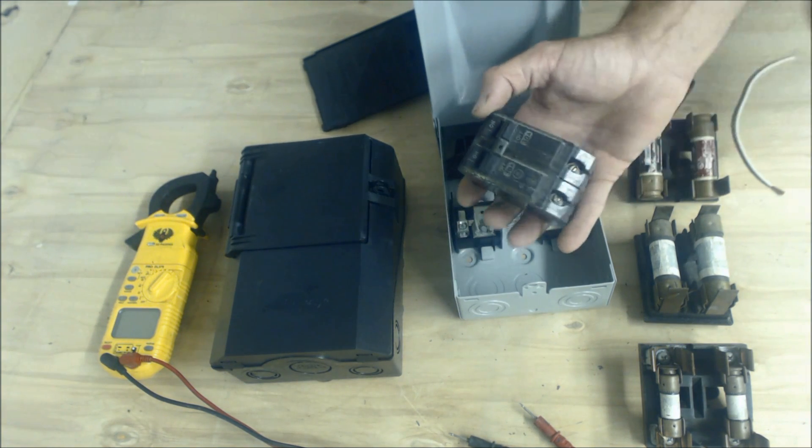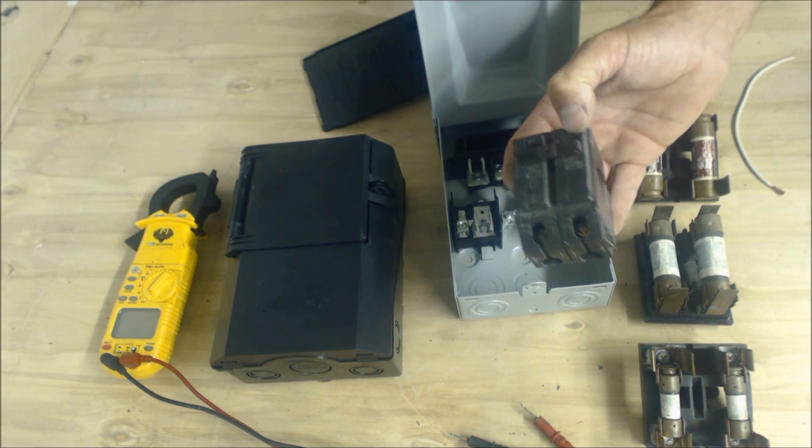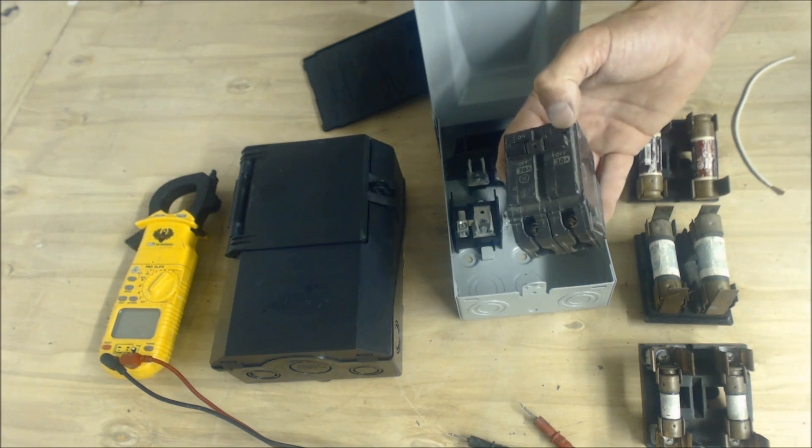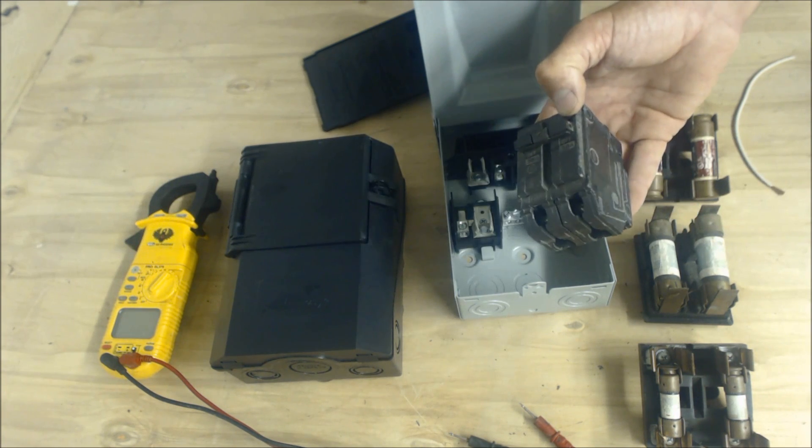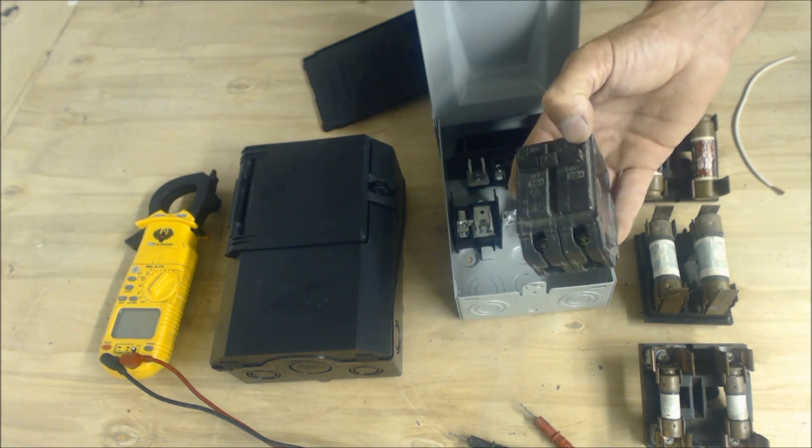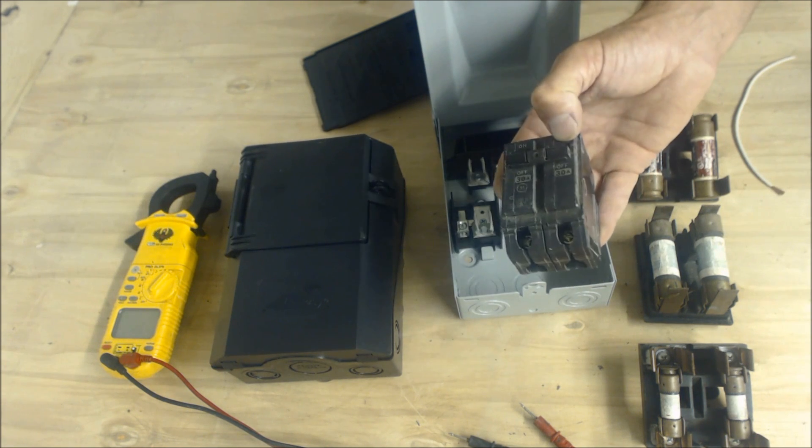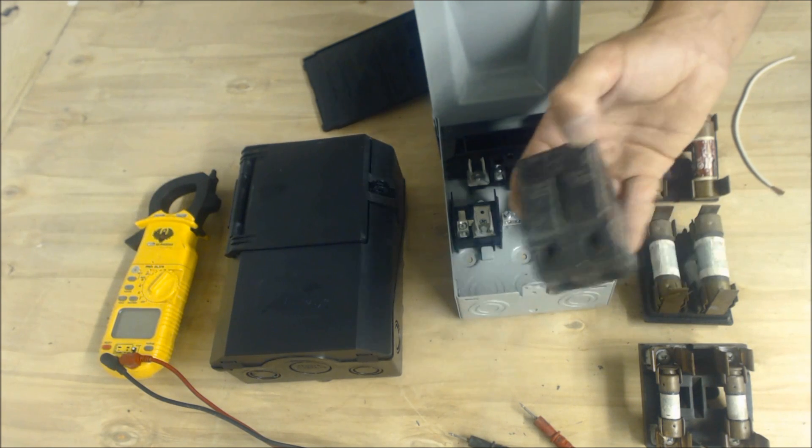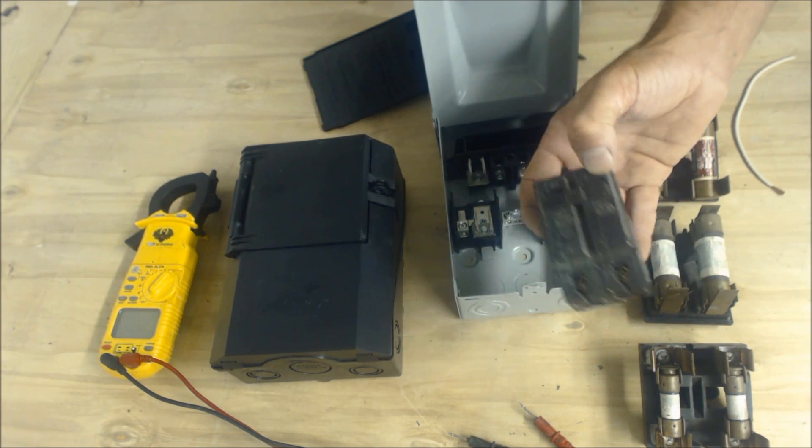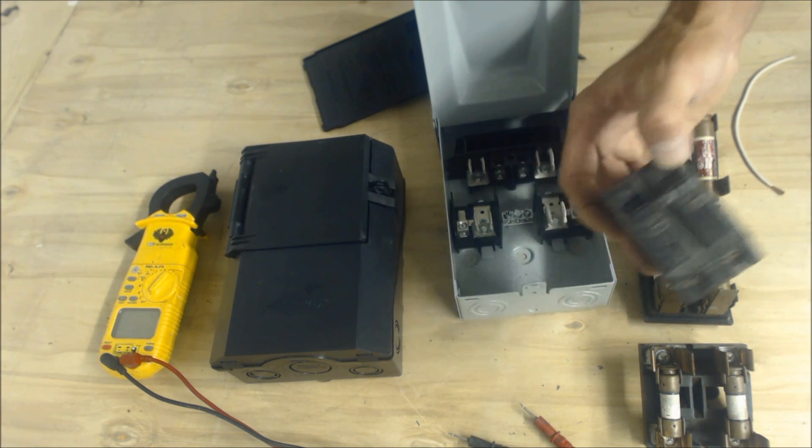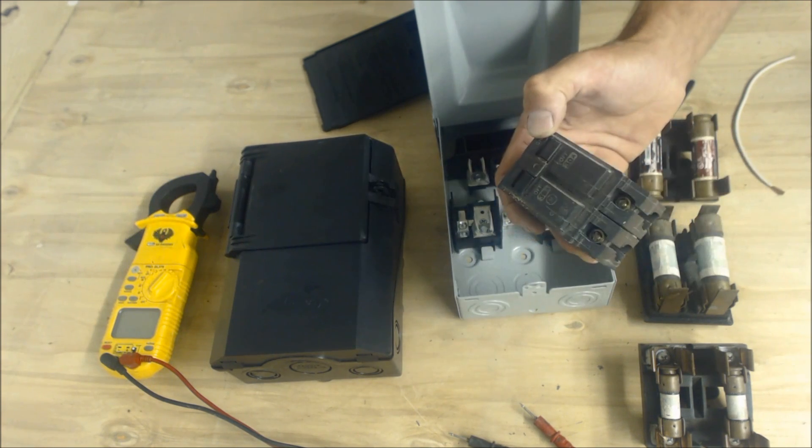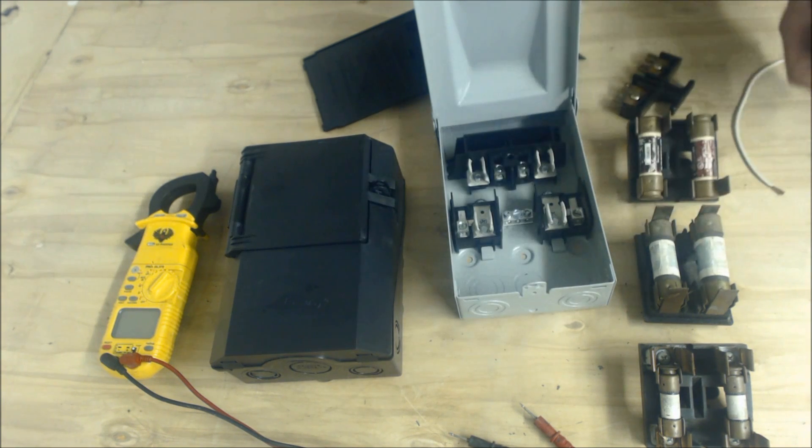Because what happens is, if an outdoor unit says the max amp rating is 30 amp, well, guess what? All of the wire inside of that unit, that outdoor unit, is rated for 30 amp. So if you have a 40 amp breaker on that, and you have wire that's in the outside unit, that's only rated for 30, potentially, if there was ever a locked compressor or something like that, before the breaker would pop, potentially the wire could get hot enough to maybe, potentially start a fire or something. So the whole point is, you're doing everything safely and correctly so that there's no excuses.